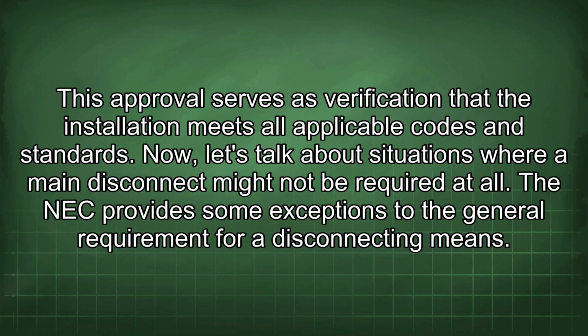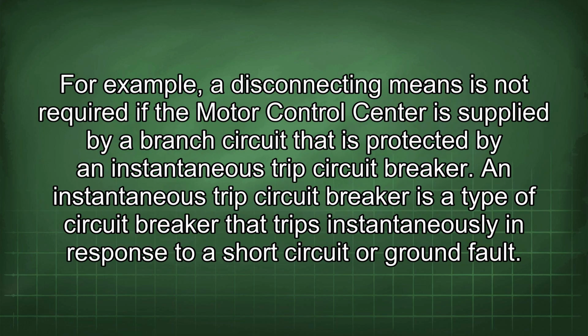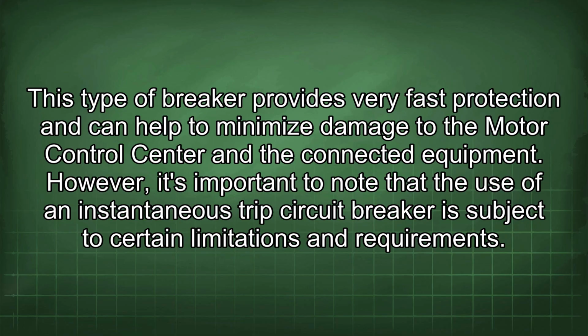Now let's talk about situations where a main disconnect might not be required at all. The NEC provides some exceptions to the general requirement for a disconnecting means. For example, a disconnecting means is not required if the motor control center is supplied by a branch circuit that is protected by an instantaneous trip circuit breaker. An instantaneous trip circuit breaker is a type of circuit breaker that trips instantaneously in response to a short circuit or ground fault. This type of breaker provides very fast protection and can help to minimize damage to the motor control center and the connected equipment.